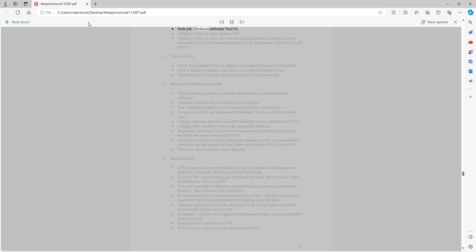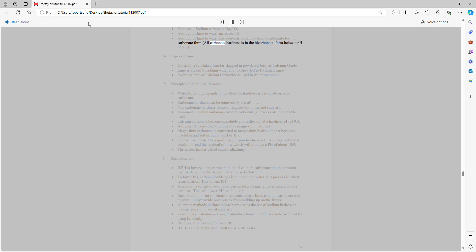Soda ash — sodium carbonate. Addition of lime to water increases pH. Addition of lime to water also converts alkalinity from bicarbonate form to carbonate form. All carbonate hardness is in the bicarbonate form below a pH of 8.3.